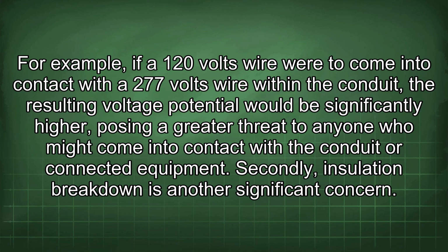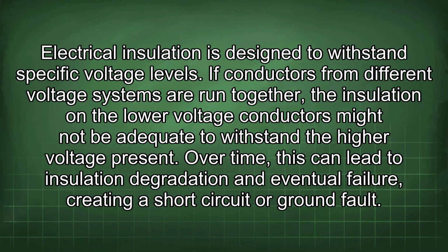Secondly, insulation breakdown is another significant concern. Electrical insulation is designed to withstand specific voltage levels. If conductors from different voltage systems are run together, the insulation on the low voltage conductors might not be adequate to withstand the higher voltage present. Over time, this can lead to insulation degradation and eventual failure, creating a short circuit or ground fault.